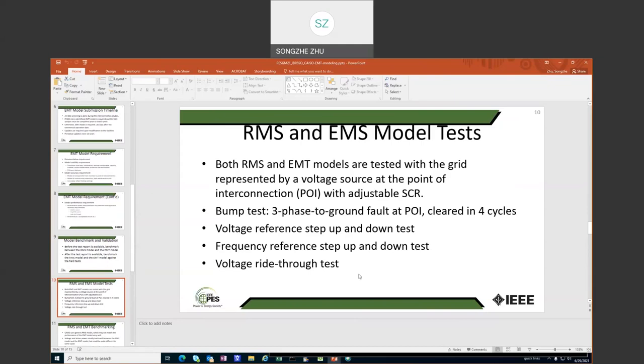So how do we benchmark and validate the RMS model and the EMT model? We run similar tests with both models, and the setups are pretty close in both tests. We set a voltage source at the point of interconnection with SCR equal to 3. Then we run a bump test. The bump test is a three-phase ground fault at the point of interconnection, typically cleared in 4 cycles. It's adjustable based on the interconnecting voltage level. Then we do a voltage reference step up and down test to verify the small disturbance watt-var control. And we run a frequency reference step up and down test to verify primary frequency response.